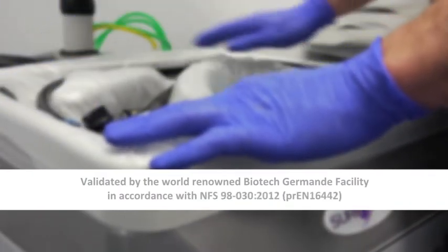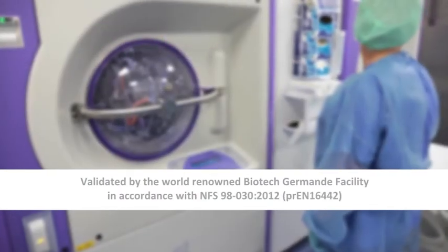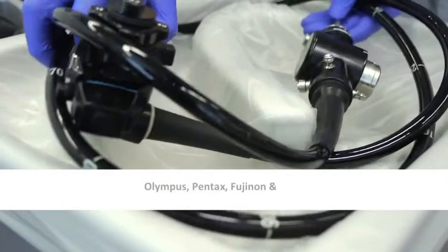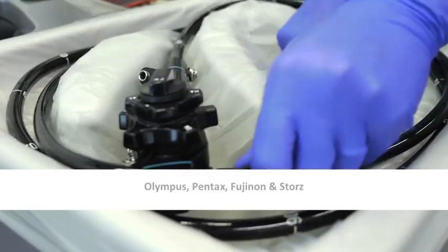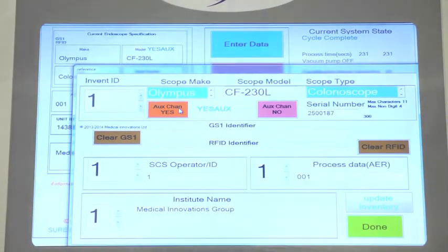Independently validated by the renowned Biotech Germande Facility in accordance with the requirements of NFS 98030 2012, the system has been extensively tested with endoscopes from leading manufacturers including Olympus, Pentax, Fujinon and Storz. Results have shown no damaging or detrimental effect on the endoscope.